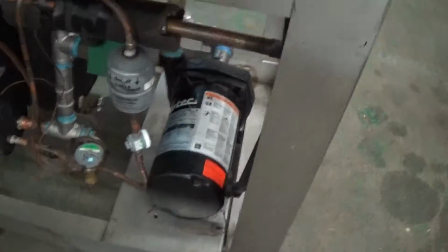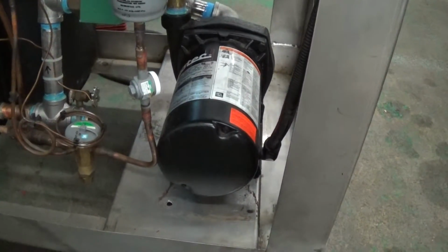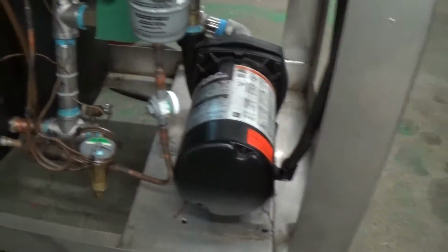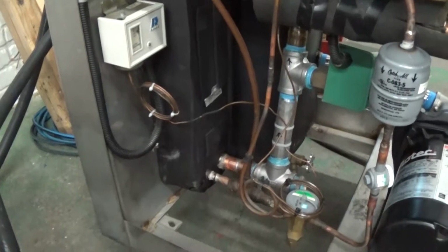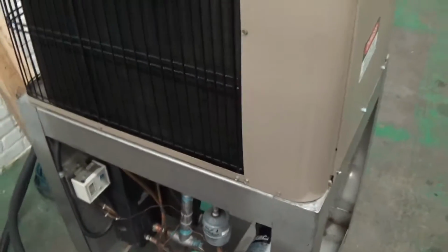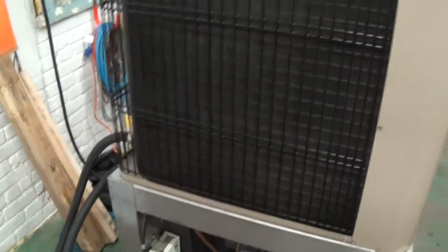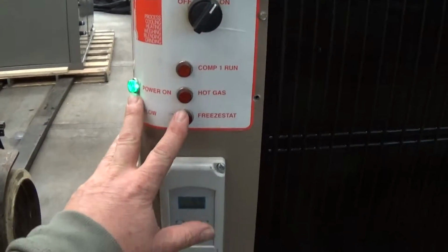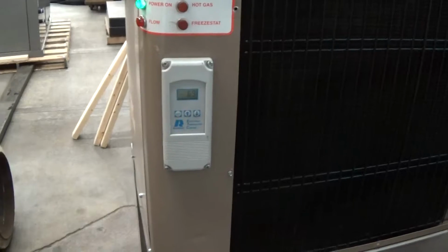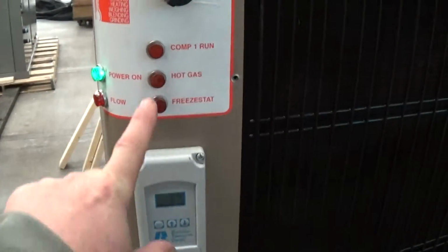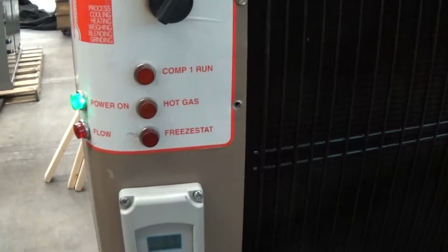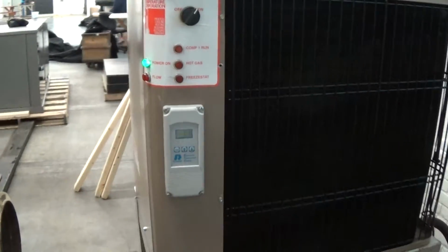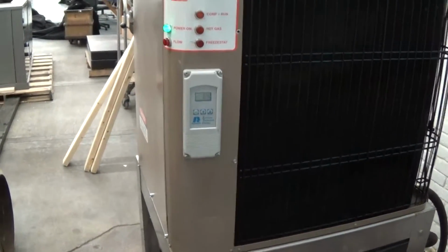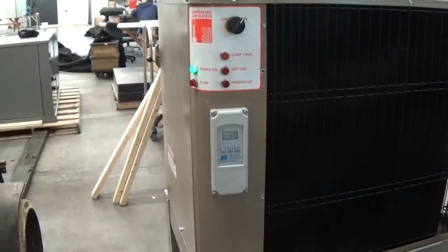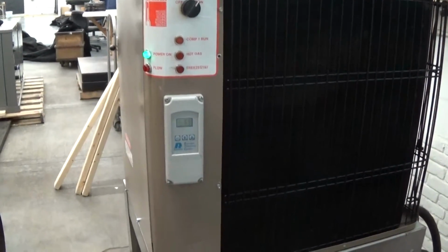This unit has a brand new 1 horsepower, I'm sorry, I think it's a 1/2 horsepower process pump, and a brand new heat exchanger, which was part of the delay, quite frankly. It's gone through some repainting and cleanup of the grills. It has all new indicator lights that were fixed and debugged, and this has a 2-stage Ranco controller. The reason it has a 2-stage controller is because it has a hot gas option, which is when you get down to your set point temperature, it helps create a false load internally, which minimizes the amount that the compressor cycles on and off.